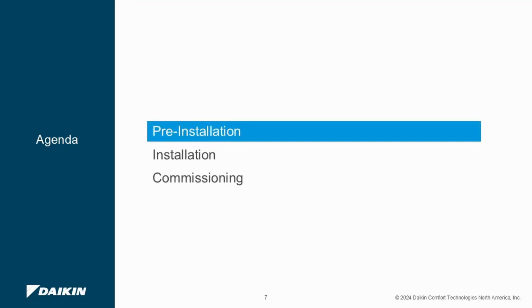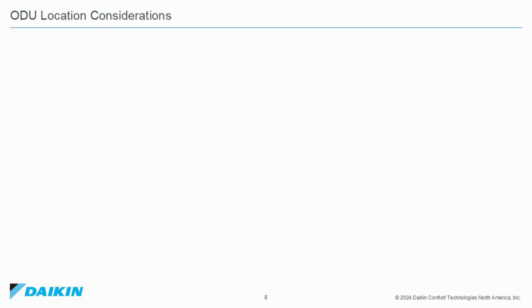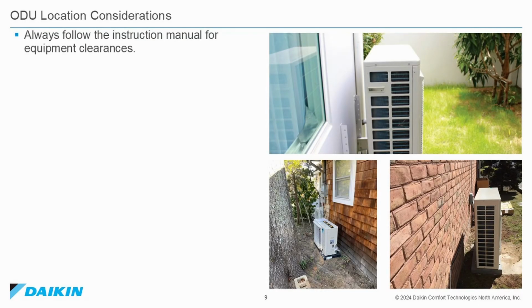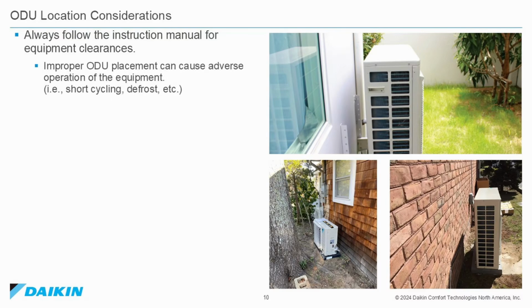Training Agenda: Pre-installation, Installation, and Commissioning. Let's start with pre-installation. Outdoor unit location considerations. Always follow the instruction manual for equipment clearances. Improper outdoor unit placement can cause adverse operation of the equipment, for example, short cycling, defrost, etc.